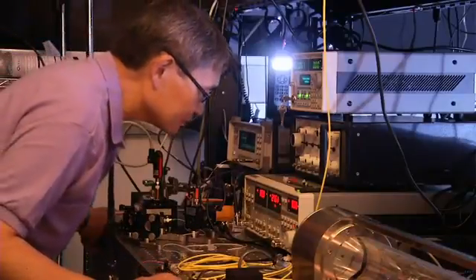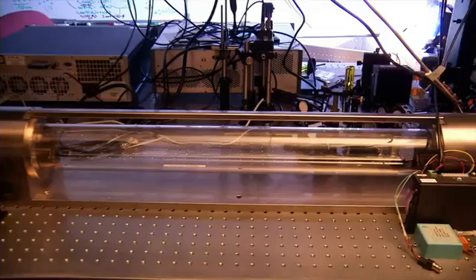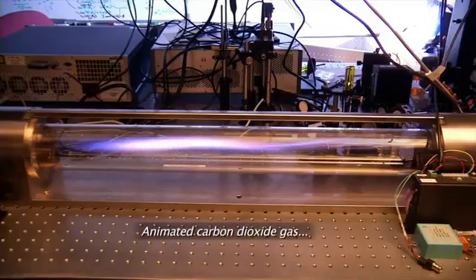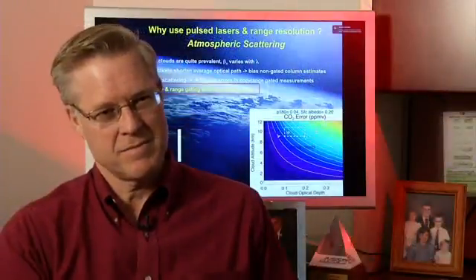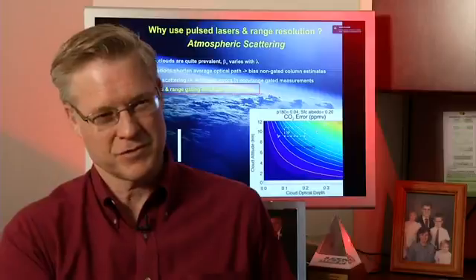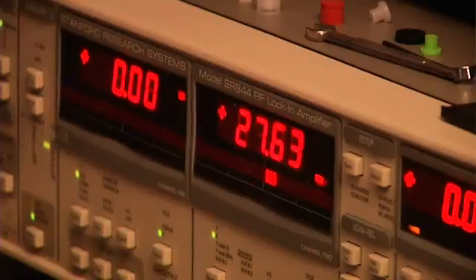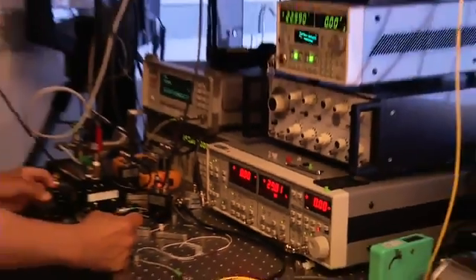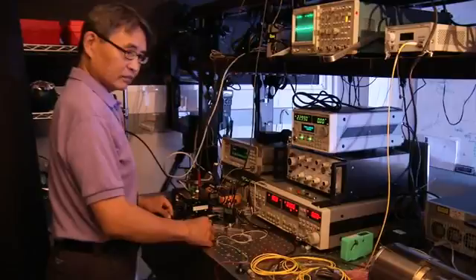The way that we evolved the carbon dioxide instrument is we use a small gas cylinder. By doing that, we can put a controlled amount of carbon dioxide in there, basically 100%. It allows us to make that measurement, which we're ultimately going to measure from space, in a controlled way, not using air, but with a big absorption in a very small physical footprint, so we can do the measurement on our lab bench.